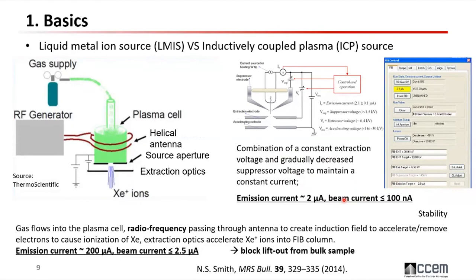Keep in mind that for the gallium source, to maintain a stable beam current you need to adjust these parameters periodically and may even need to re-flash your source sometimes, which is problematic for long-duration tomography runs.